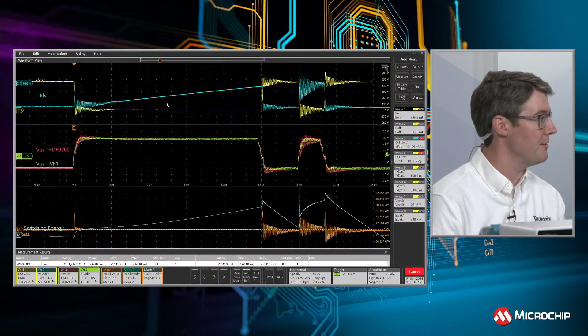I wanted to just comment a little bit about how we picked the 50 microseconds and the 2 microseconds. If you look at the blue trace on the waveform here, that's the drain current. And because there's a certain inductance that is in series, between the power supply and the MOSFET, the longer that you take to charge up the inductor, of course, the higher the current. And this is how you set the current for the test, right? If we wanted more than 300 amps, we would just extend that 50 microsecond time. If we wanted lower current, we would make it shorter.